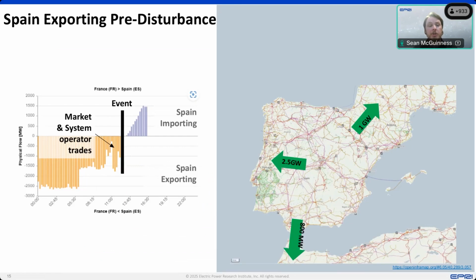And you can see here on the left the change in flow on the connector between France and Spain. Initially Spain had been exporting to France quite substantially during the night, and that reduced. But in that 9 a.m. to 12 noon window, you can see quite a lot of flow due to market and system operator trades occurring. So there's quite a lot of change on that interconnector. It was roughly 1 gigawatt a few minutes before, and then trading reduced it close to 0 just immediately prior to the event. We give that as context to say that it was not operated strictly in steady state; there was a lot of variation on the interconnectors due to that trading.